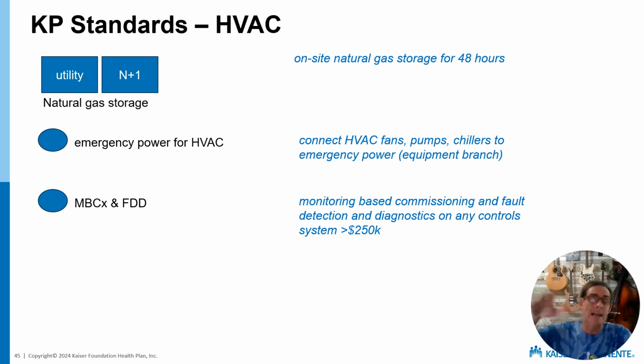But certainly, last but certainly not least, is monitoring-based commissioning and fault diagnostics. The single best thing that we can do for resilience is good maintenance. So we do have a requirement in our standard that anytime we're doing more than $250,000 worth of controls, we would add monitoring-based commissioning, fault detection, and diagnostics to the building. Kaiser does have an enterprise agreement with the monitoring-based commissioning provider, which is Clockworks.